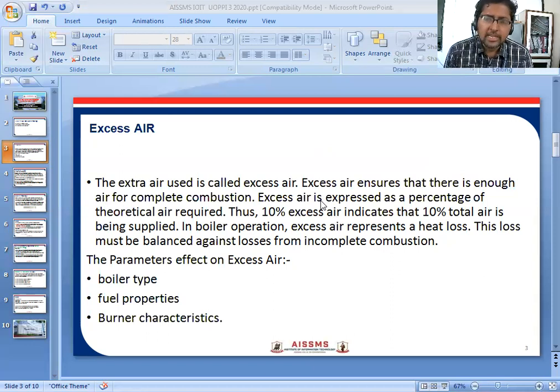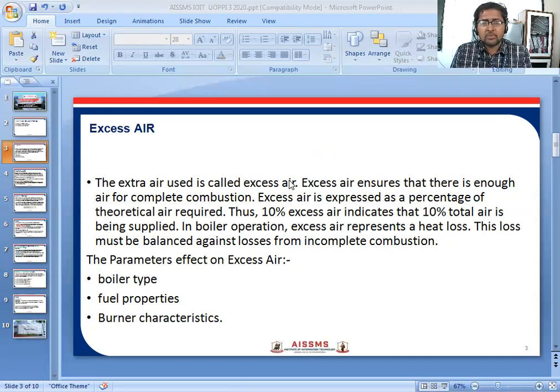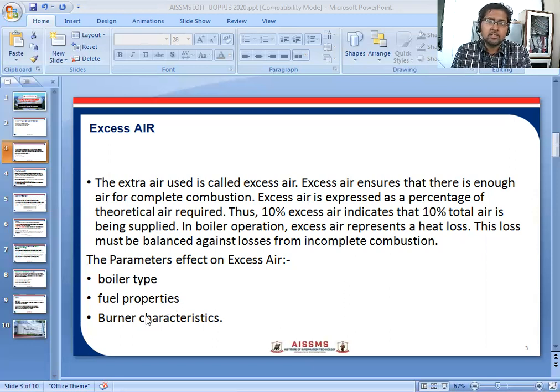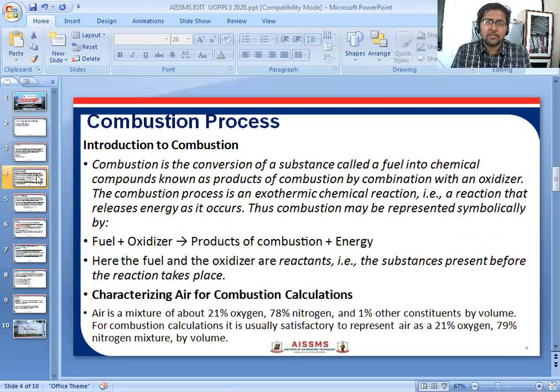Extra air is required in boiler operation because there will be some losses during operation. To compensate, some excess air is needed, typically around 10%. The parameters that affect excess air are: boiler type, fuel properties, and burner characteristics. If any of these vary, the required excess air percentage will vary accordingly.